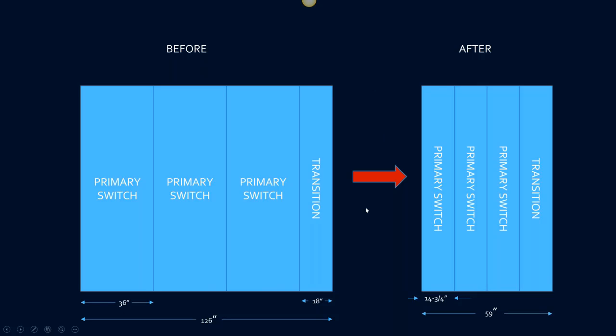So you can see the results here. I've tried to make it clear. We've gone from 126 linear inches to 59 inches without giving up any functionality at all. And the way we've done it, some of you are probably curious as to how do you fit a dozen eggs in one egg cup. These switches to the left that are air insulated, they are phase A, B, C from left to right, and the interrupting mechanism is an air interrupting mechanism. Over here to the right, the HVLCC, the phases are A, B, C front to rear, and the interrupting mechanism is an SF6 hermetically sealed device, which has been proven over, I think this has been in existence for 25 years.